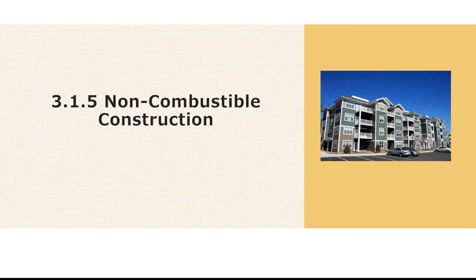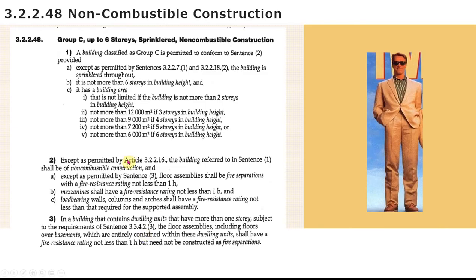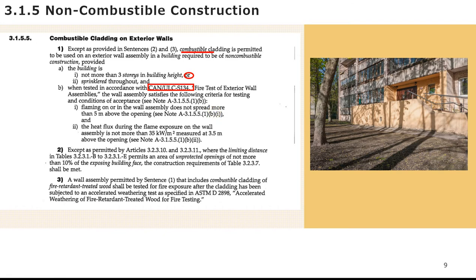Now we jump over to the non-combustible construction section. Everything is non-combustible construction here. Combustible cladding is permitted on the exterior wall of a non-combustible building, provided the building is not more than three stories in height or is sprinklered throughout, and the entire wall assembly sandwich is tested to S134. That tells us the rules in the non-combustible construction section.